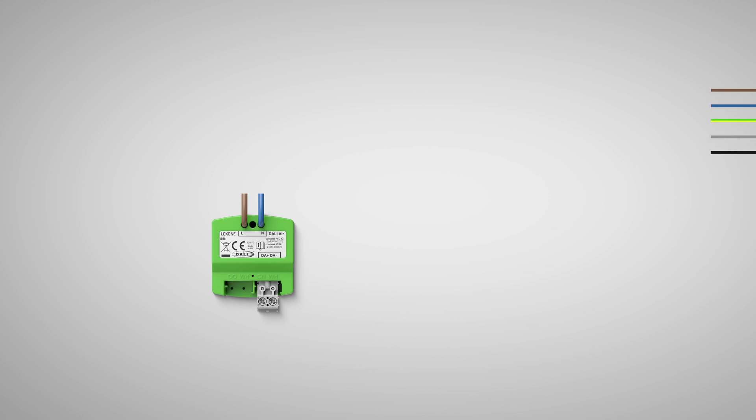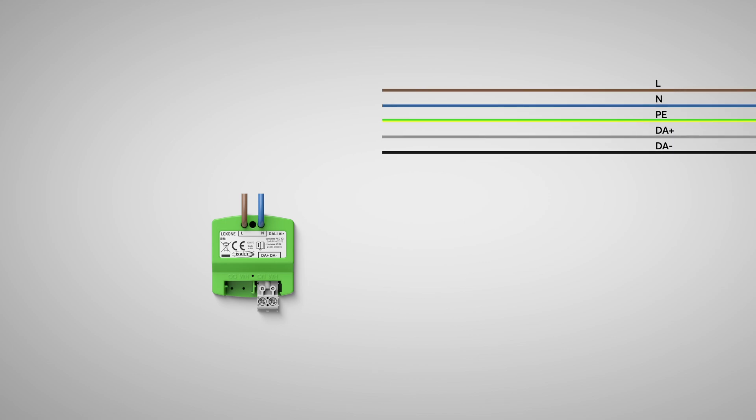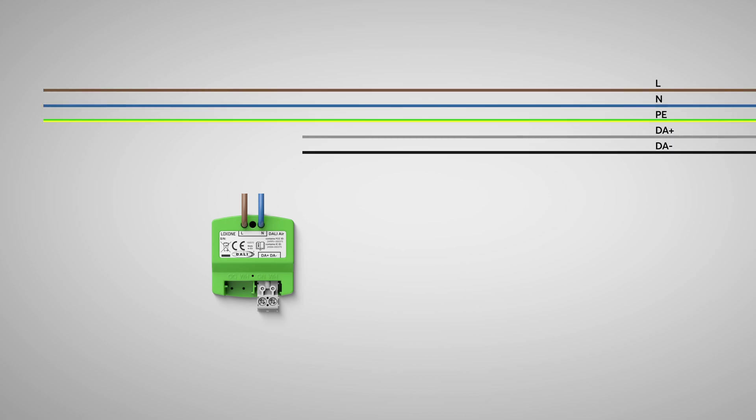Let's take a closer look at the wiring of the DALI Air. The DALI 2 wire technology is usually laid parallel to the 230V in the same cable. The DALI Air is powered via the two wires, brown and blue, with 230V. The two remaining wires, black and grey in my case, are used for the data connection, which is not polarity bound by the way.